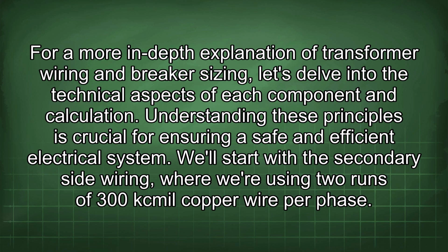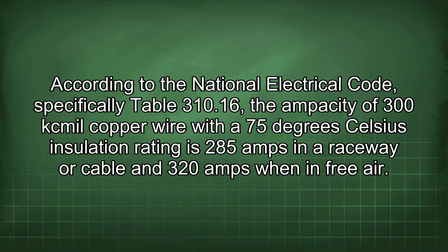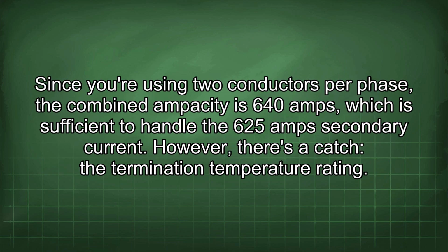We'll start with the secondary side wiring, where we're using 2 runs of 300 kcmil copper wire per phase. According to the National Electrical Code, specifically Table 310.16, the ampacity of 300 kcmil copper wire with a 75 degrees Celsius insulation rating is 285 amps in a raceway or cable and 320 amps when in free air. Since you are using 2 conductors per phase, the combined ampacity is 640 amps, which is sufficient to handle the 625 amp secondary current. However, there's a catch: the termination temperature rating.